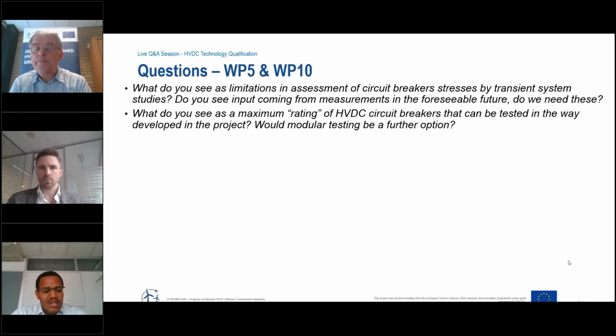Well, the second question is about modular testing. Modular testing is definitely one of the ways out, especially as the rating goes up. As I said, we are limited to 500 kV DC circuit breakers. So beyond that, how do we test? I think we will opt for modular testing. But we have to be careful when we say modular testing. It depends on the design of the circuit breakers, because modular testing doesn't mean that in all designs you are just cascading circuit breakers in series. If that's the case, maybe you can test 2-3 modules, and then you can see the sharing of stresses and the operation of each module at a time.